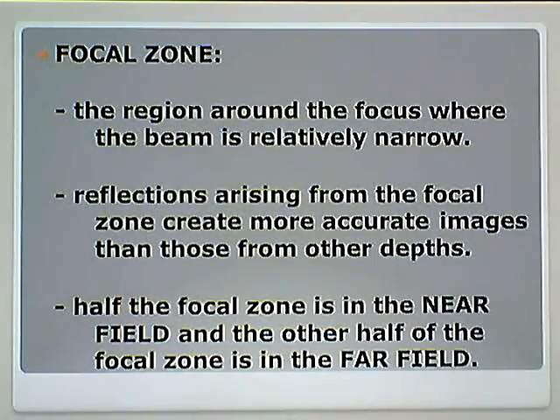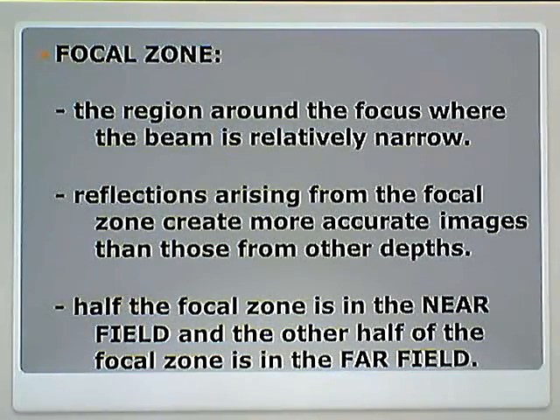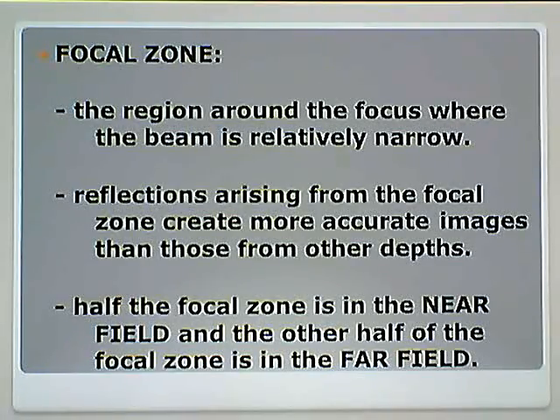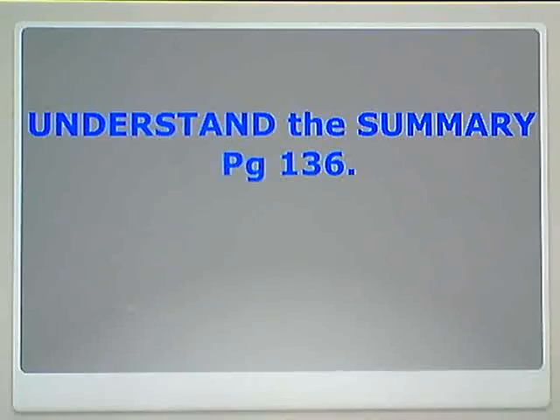The focal zone is the region around the focus where the beam is relatively narrow — the area from the focus and everything very close to it. Half of the focal zone lives in the near field, and the other half lives in the far field. So if the focal zone measures four centimeters, two of those centimeters are in the near field and the other two are in the far field. For a brief summary of all these descriptive terms, look at page 136, read it, understand it, and you will be just fine.